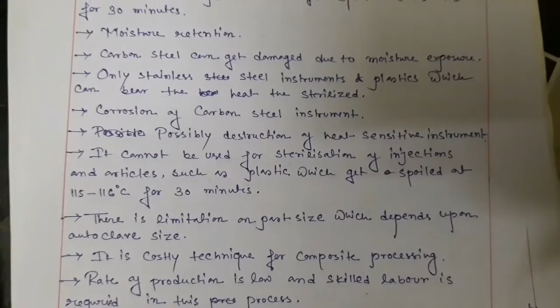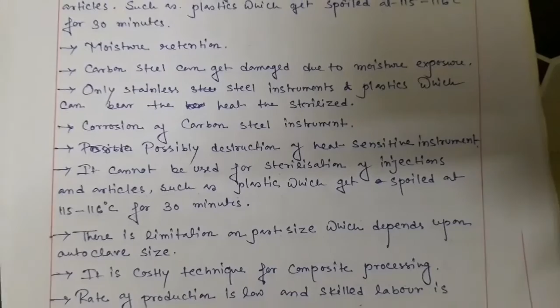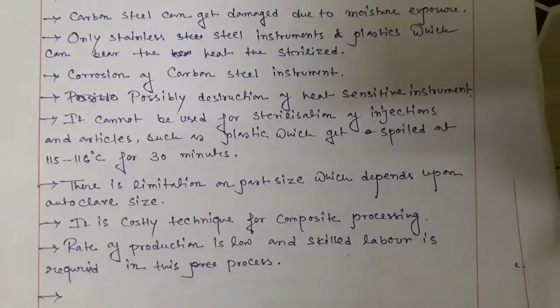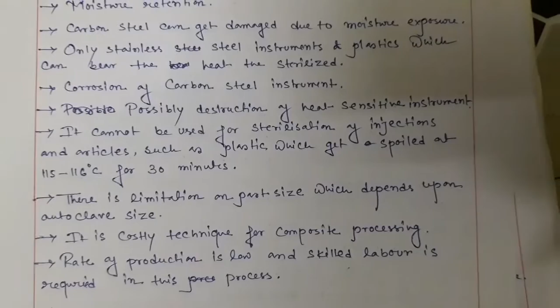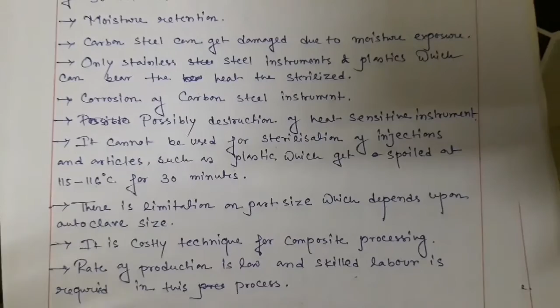And possibly destruction of heat sensitive instruments, obviously. And it cannot be used for sterilization of injection articles such as, as I already told, plastic, which gets spoiled at 115 to 116 degrees centigrade for 30 minutes. If you choose plastic, the exceptions are nylon and PVC. Without nylon and PVC, any type of plastics are not sterilized in this condition. And there is a limitation on part size, which depends upon the size of the autoclave.